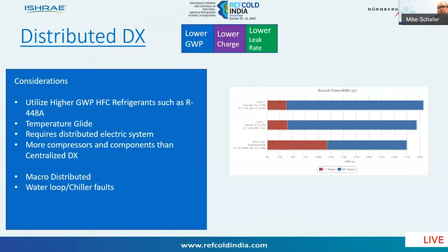And then for the macro distributed, certainly you have to take care to make sure that you don't have chiller or fluid cooler faults that would affect the entire store or all the systems that are hooked to it. And then in terms of the power distribution or the annual power consumption, very similar to what we've seen previously. Distributed would be the lowest power consumption in this case compared to booster CO2 and a cascade CO2 system in the simple examples that we've been talking about.